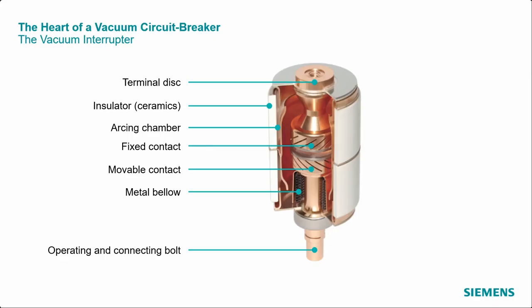The arcing chamber, here made of copper, encases the place where an electric arc forms when the contacts within the breaker separate or come together. The copper provides excellent conductivity and helps dissipate the heat generated by the arc. This is essential for extinguishing the arc quickly and preventing damage to the system. The fixed contact is a static, unmovable contact that is connected to one of the terminal discs. When the breaker is closed, it creates an electrical connection by touching the movable contact. In an open state, it is separated from the movable contact, interrupting the flow of the current.